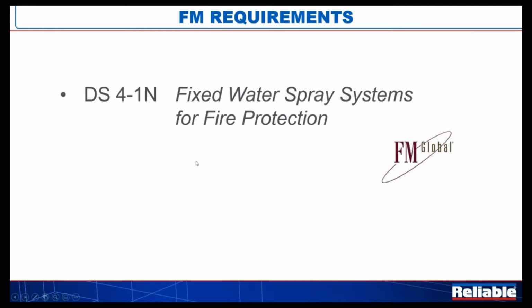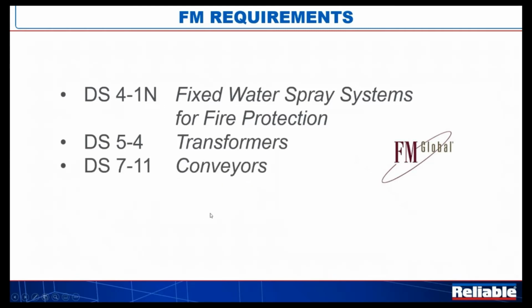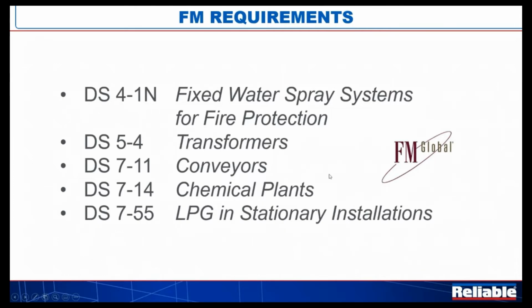Well, Factory Mutual has adopted NFPA 15. Now, it says that right in the front of their data sheet 4-1N that they have adopted NFPA 15, but as they are wont to do and have the rights to do, they've taken some things and moved them around here and there, and then they also give us some additional data sheets to work with. By reference, it would reference us to transformers in data sheet 5-4, 7-11 for conveyors, 7-14 for chemical processing plants, and then 7-55. And these are just some examples for your tanks that are essentially in what we call stationary installation.